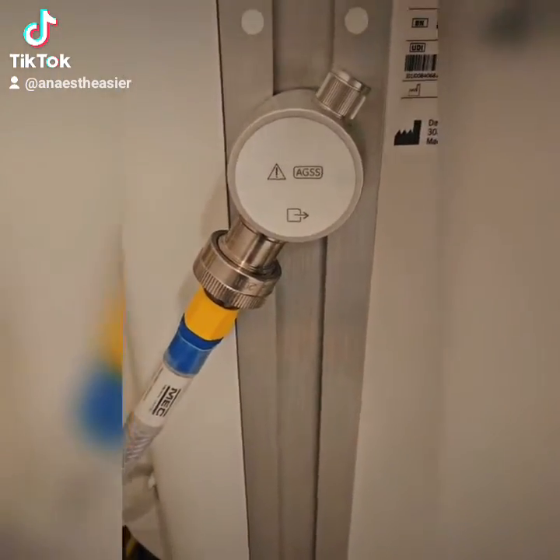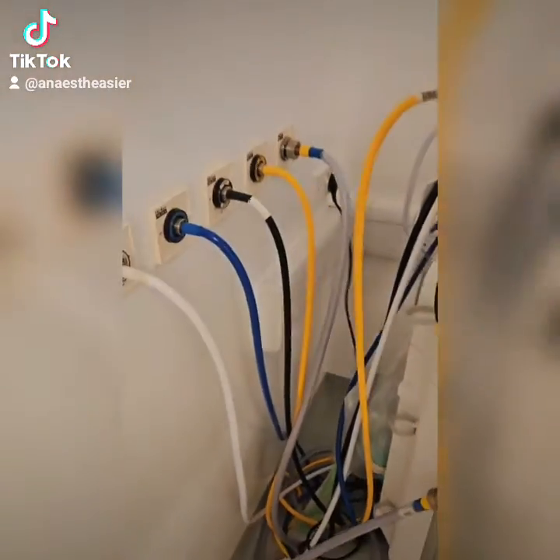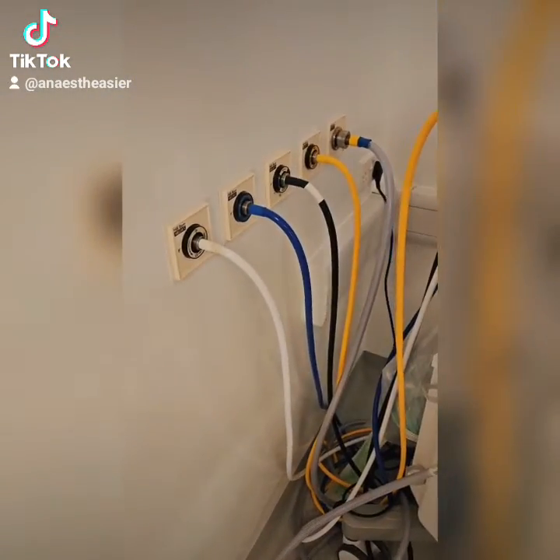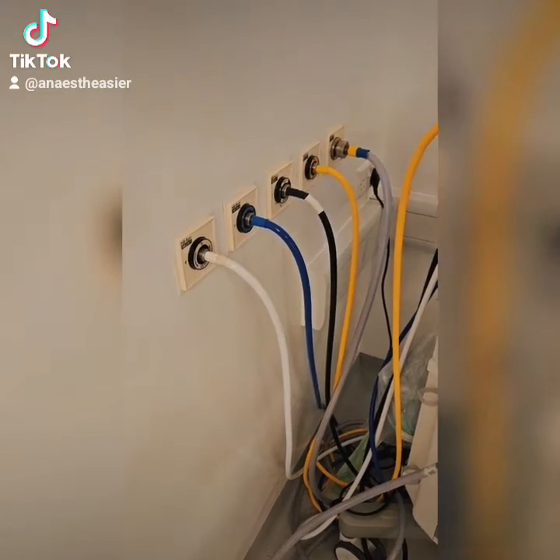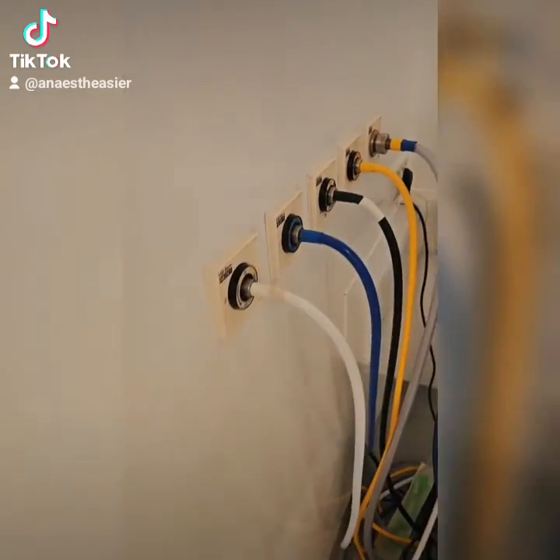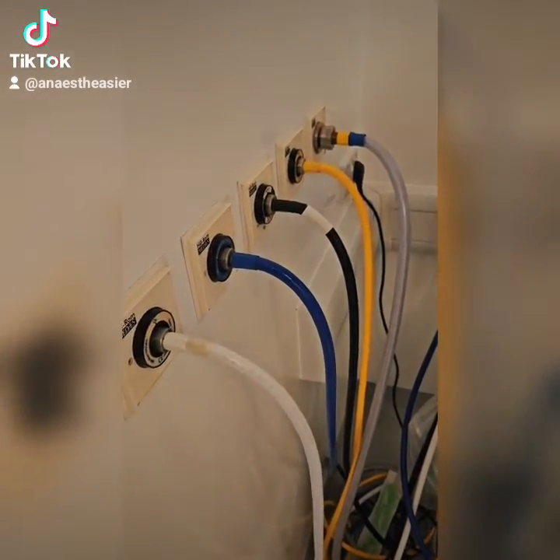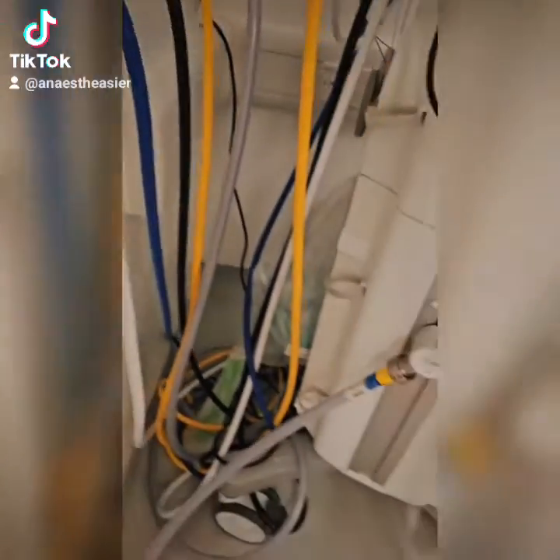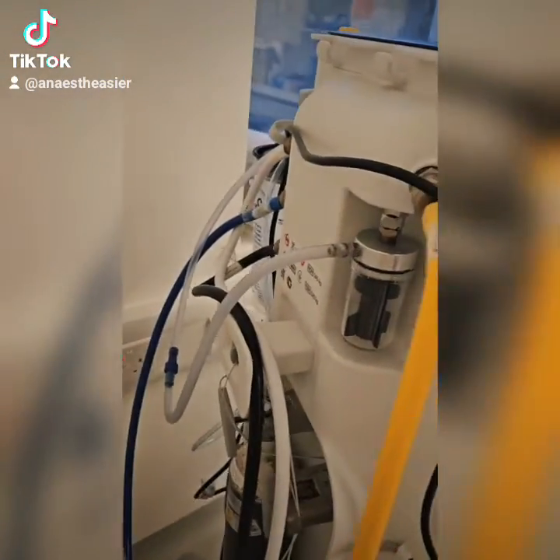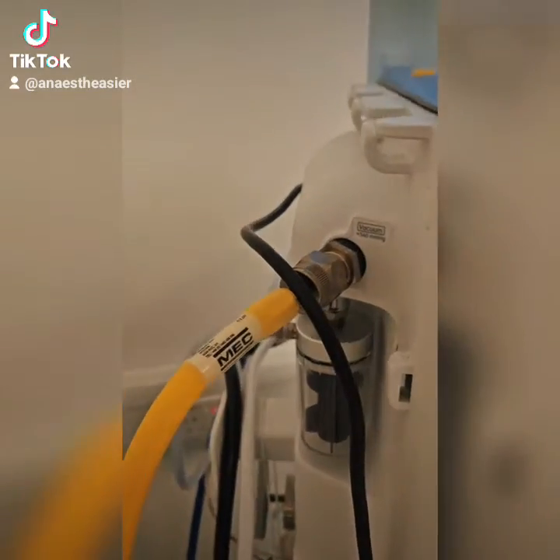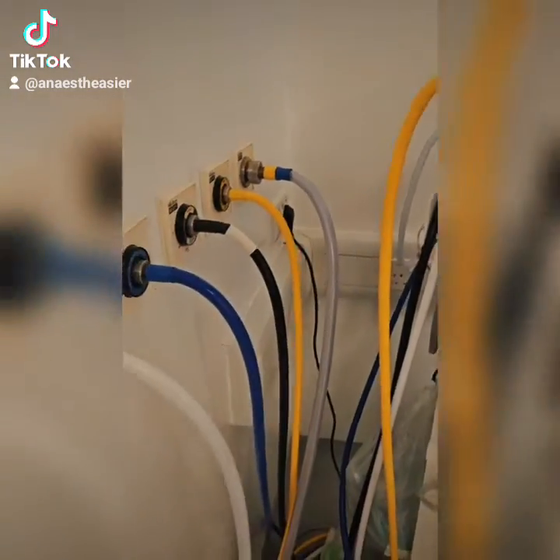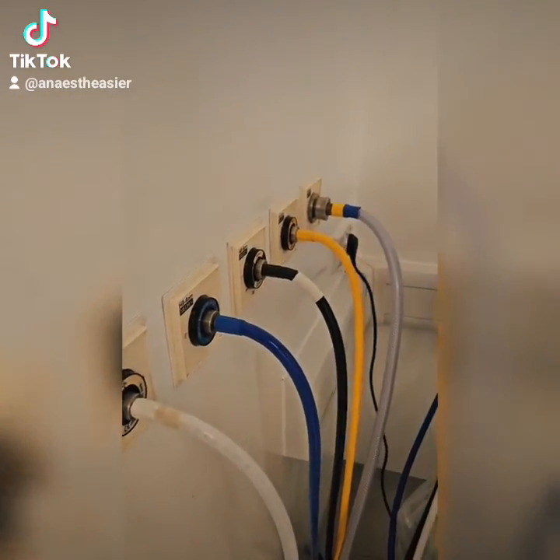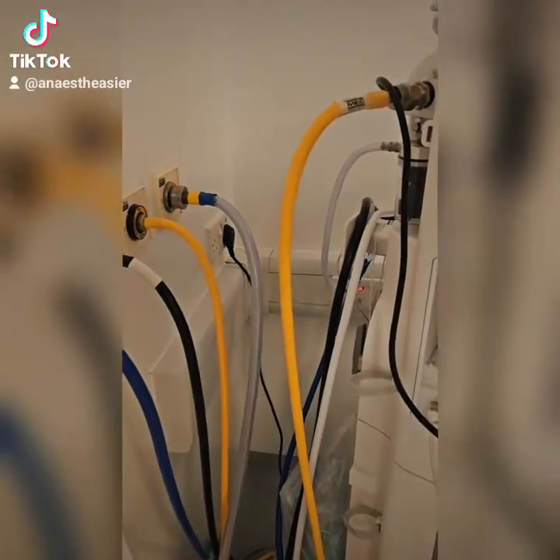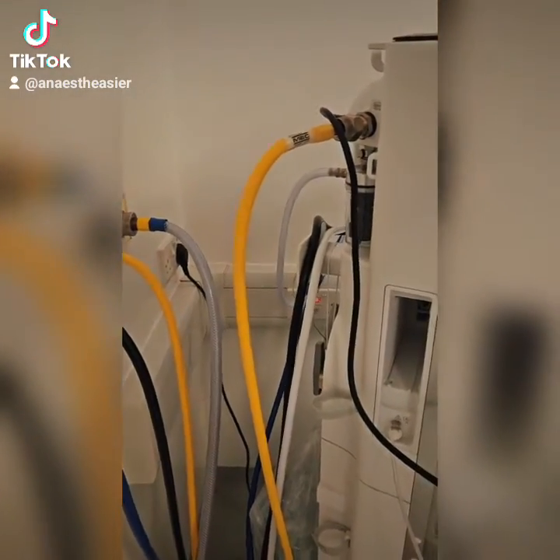This is a special module on the side of the machine, which is trying to be better for the environment by suctioning up all the anaesthetic gases and preventing them from just being lost out into the atmosphere. So your oxygen and your nitrous, etc., all plumb down here into the back of the machine. They all have unique screw threads, which means you can't plug the wrong cable into the wrong wall socket, which means that you can't accidentally give the wrong gas. So that's one of the key safety features on the machine.